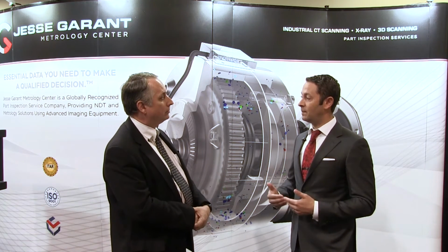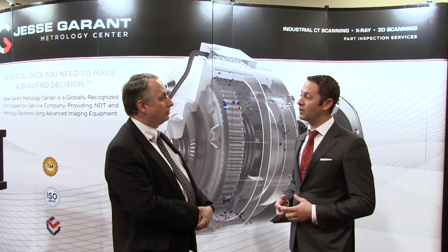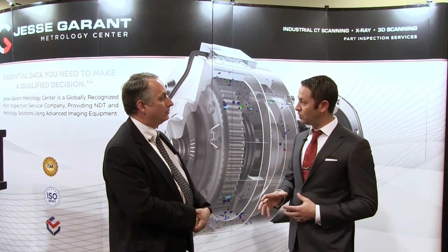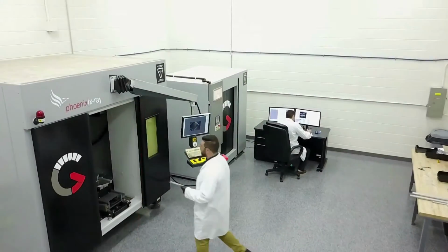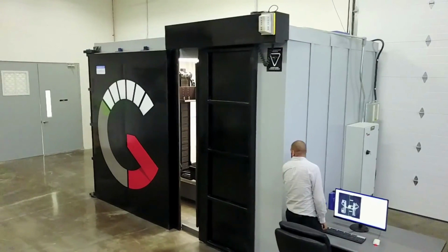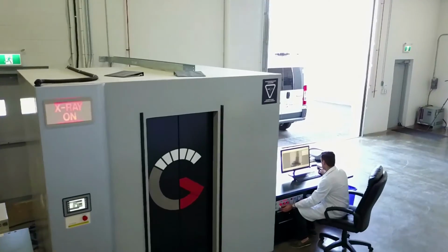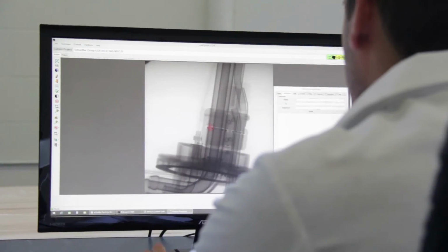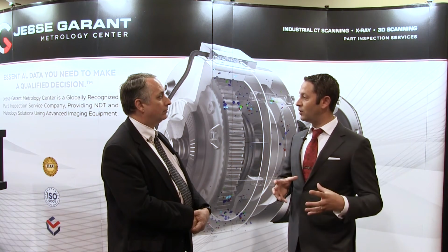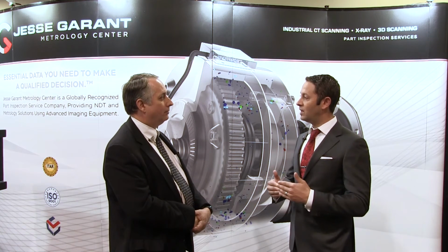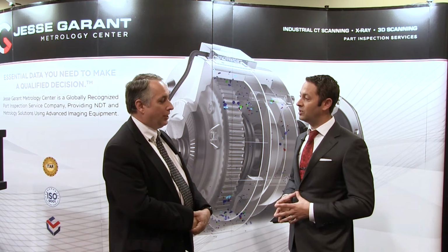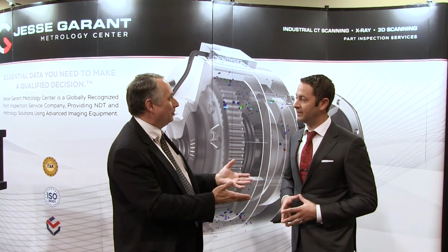Yes, resins, ceramics, a lot of composite weave, carbon fiber weave for inspection. We get into circuit board inspections for parts, epoxy overmolded applications as well. We get into lower density alloys, aluminums, titaniums, a very great application for CT. Once you start to get over the super alloy threshold and getting into your tungstens, your leads, your golds, it becomes a technology that requires so much power to shoot through the part, we lose a lot of resolution. So it's a trade-off and not particularly applicable for a lot of those higher energy alloys. So those are shielding materials to start with.